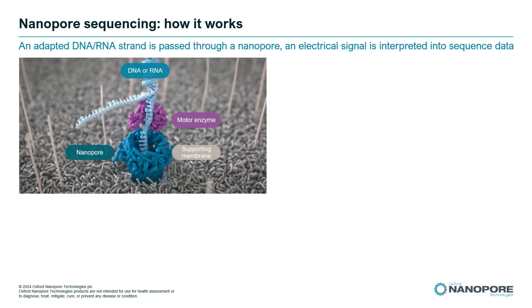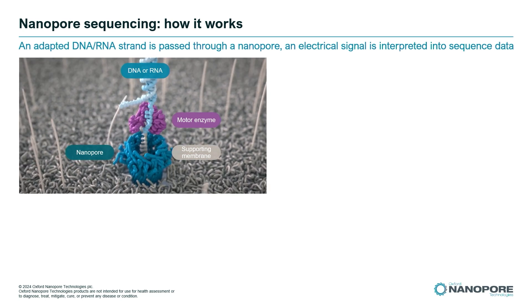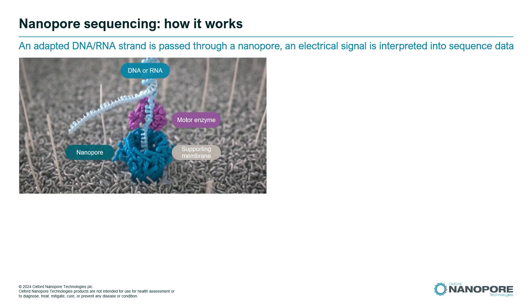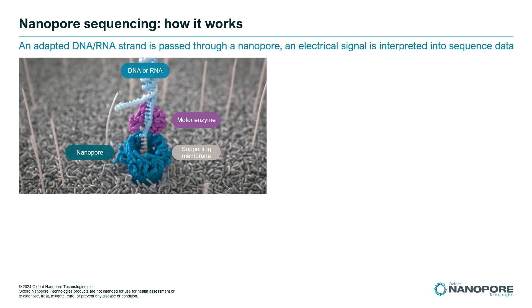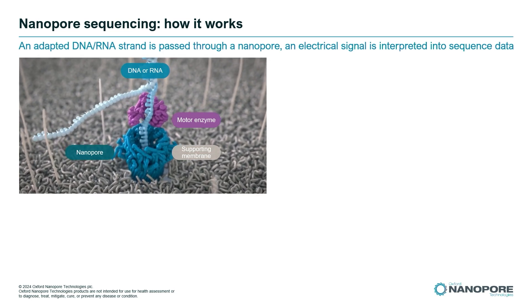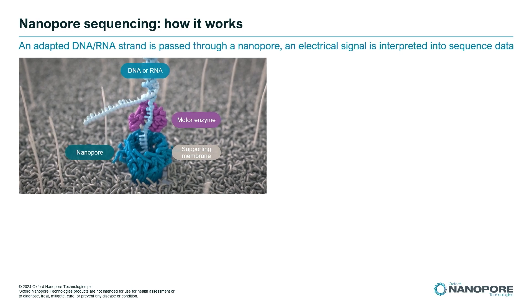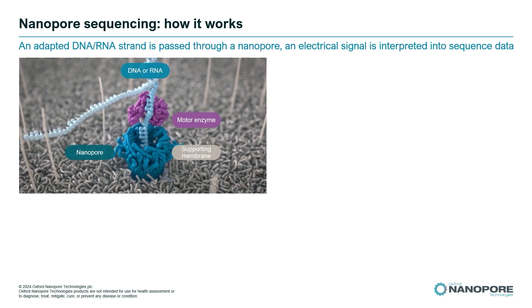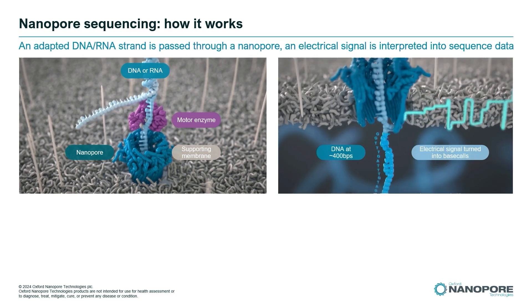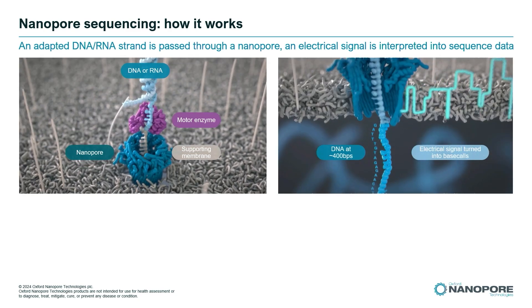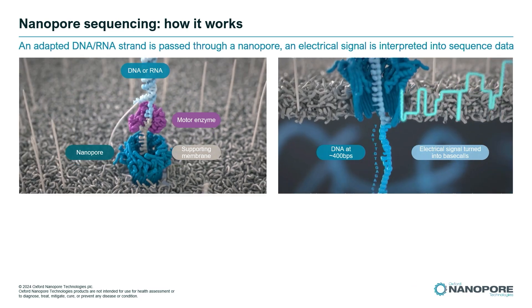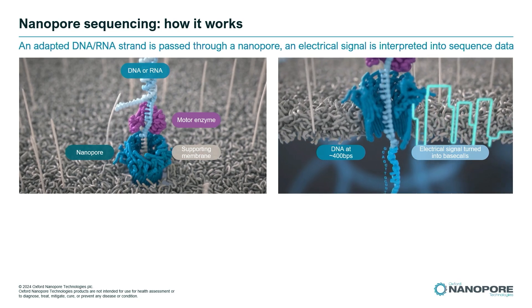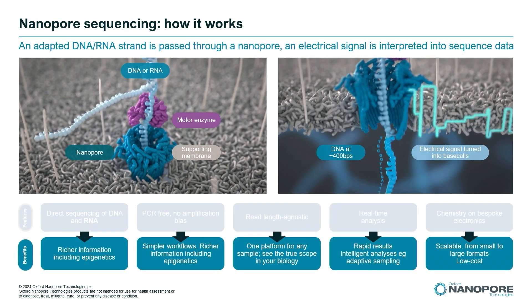Nanopore sequencing is unique in that we utilize a protein nanopore — this is the heart of our platform. It's a protein nanopore sat in a supporting membrane, and we bring the DNA or RNA to that pore, load it through a motor enzyme, and thread it through the hole in the middle of the pore. We pass current through the pore, and that DNA or RNA blocks that current to different amounts, producing an electrical signal — a trace we call a squiggle. This squiggle we turn into base calls: As, Ts, Gs, Cs, or modifications. We're able to read native or amplified DNA or RNA.